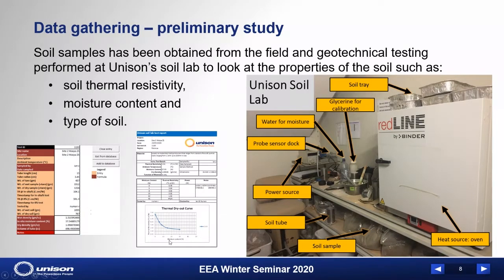The axis on the bottom is moisture content. If you have very dry soil, you get very high thermal resistivity. The more moisture content, the cooler the condition of the soil, and the lower the thermal resistivity, which is actually beneficial to the cable rating.